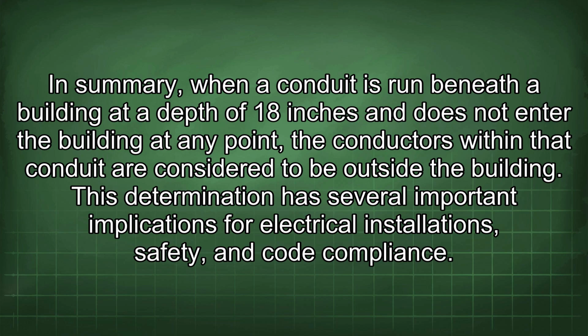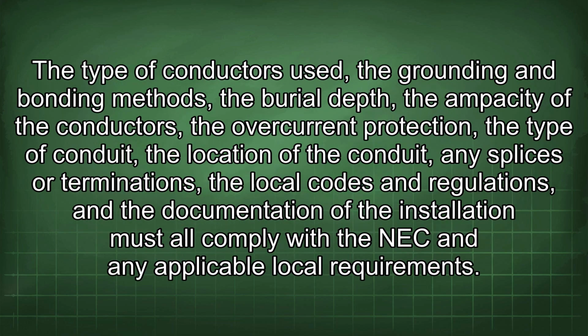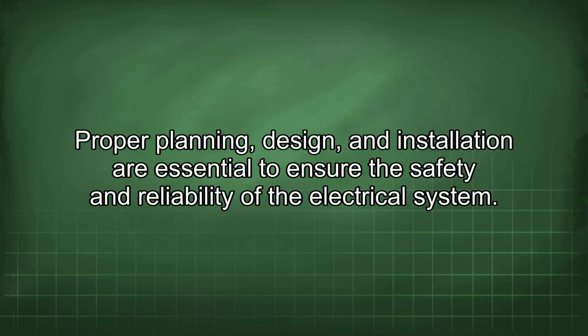In summary, when a conduit is run beneath the building at a depth of 18 inches and does not enter the building at any point, the conductors within that conduit are considered to be outside the building. This determination has several important implications for electrical installations, safety, and code compliance. The type of conductors used, the grounding and bonding methods, the burial depth, the ampacity of the conductors, the overcurrent protection, the type of conduit, the location of the conduit, any splices or terminations, the local codes and regulations, and the documentation of the installation must all comply with the NEC and any applicable local requirements. Proper planning, design, and installation are essential to ensure the safety and reliability of the electrical system.